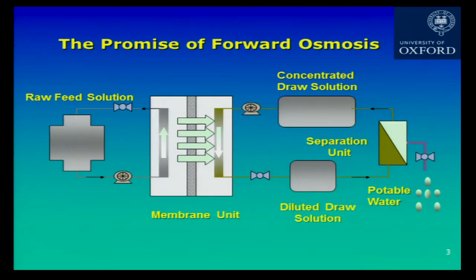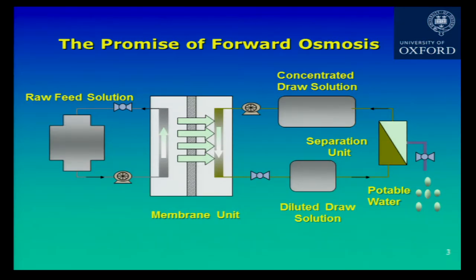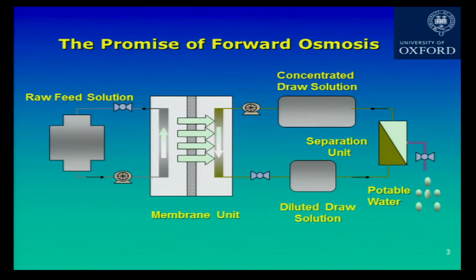This is a typical operation unit. We have a raw feed being circulated against the membrane, and on the other side a draw solution. The water is being drawn across the membrane from the feed into the draw. As the draw moves through, it gets more diluted. I then use a separation unit to recover clean potable water, and I can recycle a concentrated draw solution back into the process. In practice, you'd have a continuous feed coming in, and on the draw side a stream of potable water coming out. So this can be operated as a batch or continuous process.